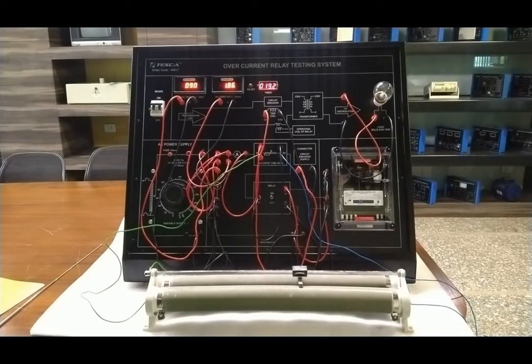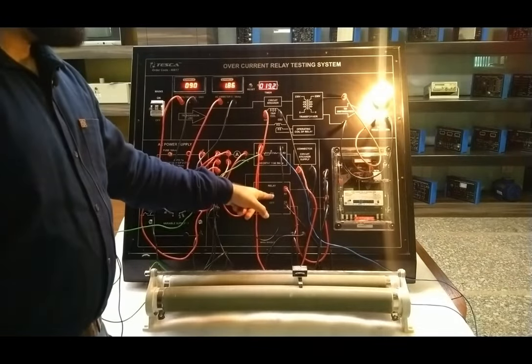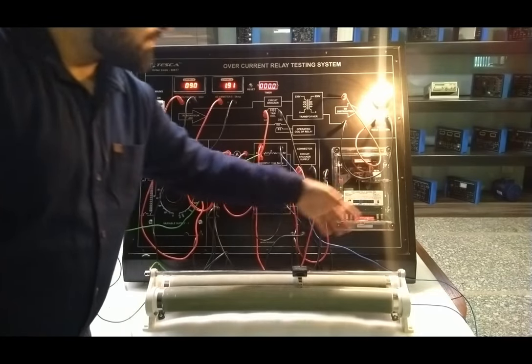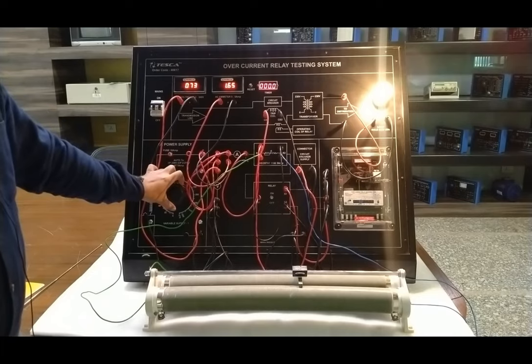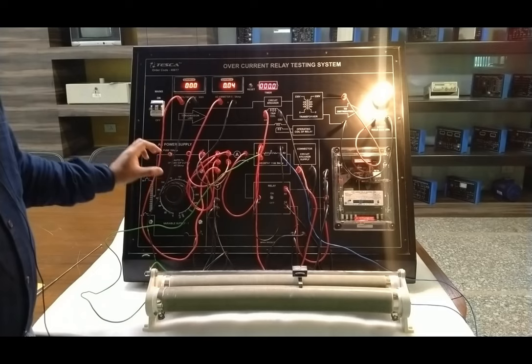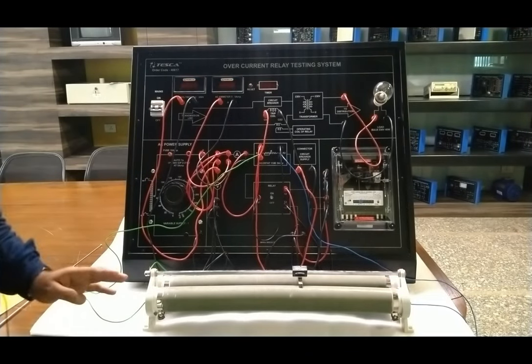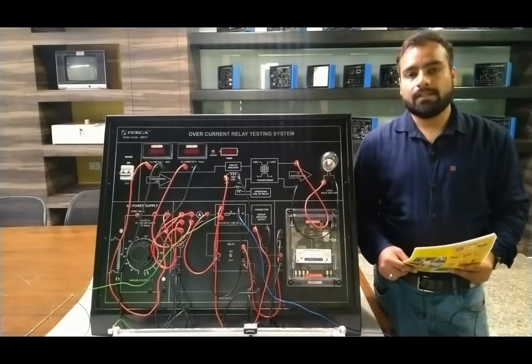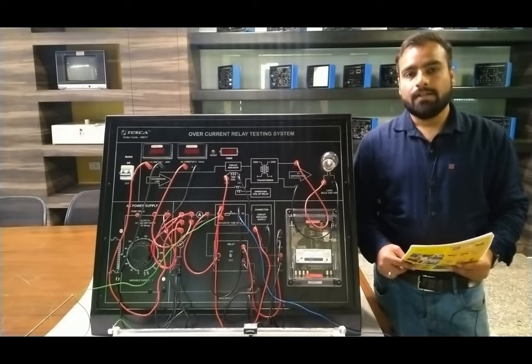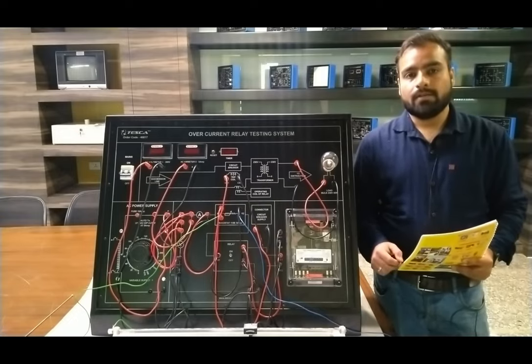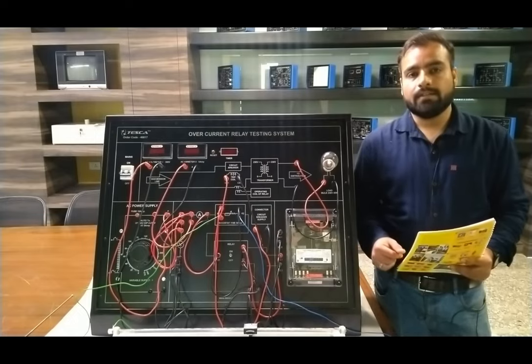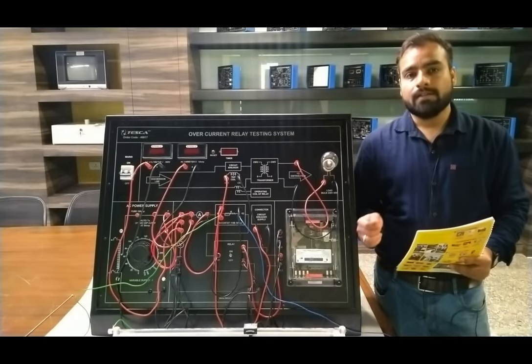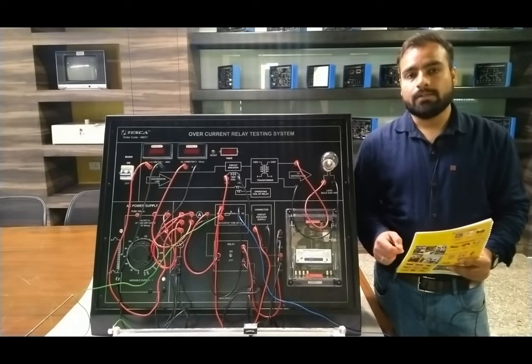After taking all the readings and completing your experiment, make sure the relay is in the off condition, reset the relay once, and decrease the voltage first using the variable supply auto transformer, then turn off the system through the MCB so that all the system should be at zero voltage and zero value, with no hazardous condition occurring whenever you turn on the circuit next time. That is how we perform the complete experiment on the overcurrent relay testing system — we have also understood how the load is controlled and protected through the overcurrent relay as the circuit breaker trips when the relay senses overcurrent, and the tripping time versus tripping current value characteristics have been observed through this practical.